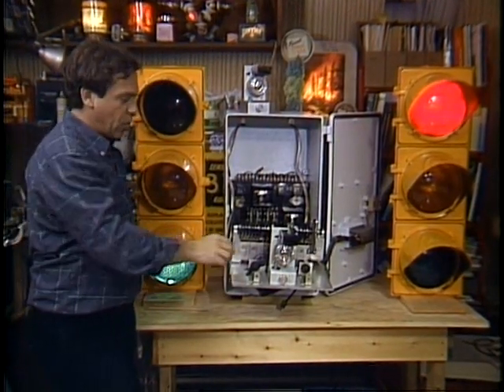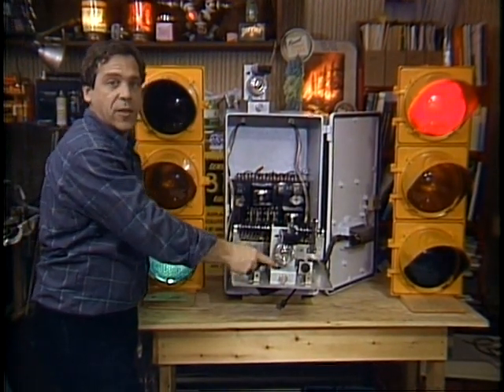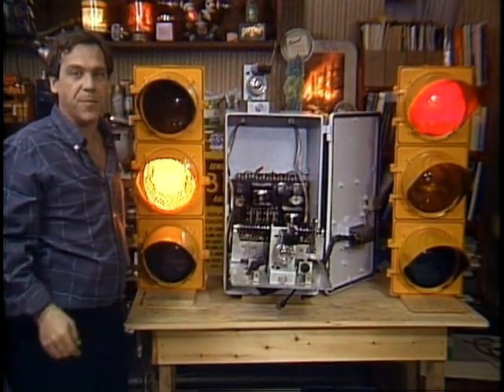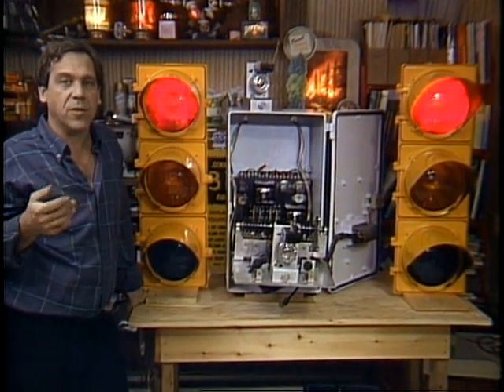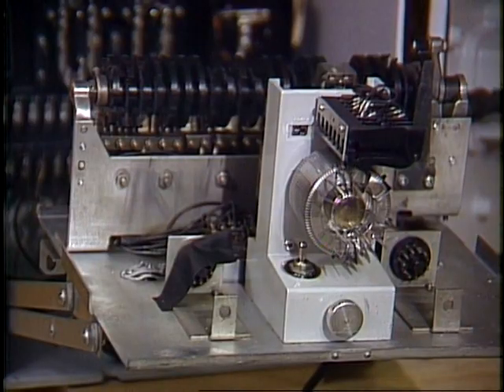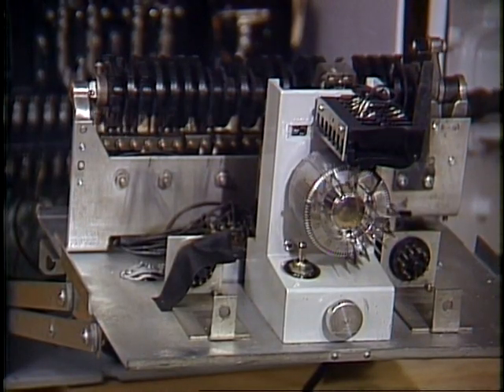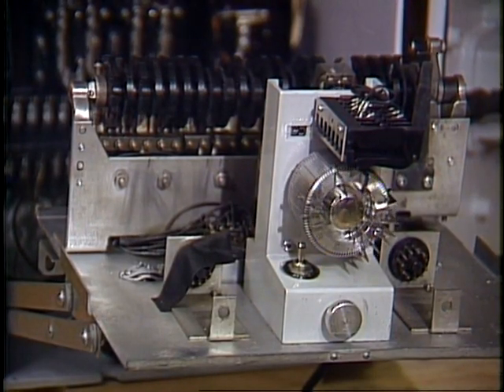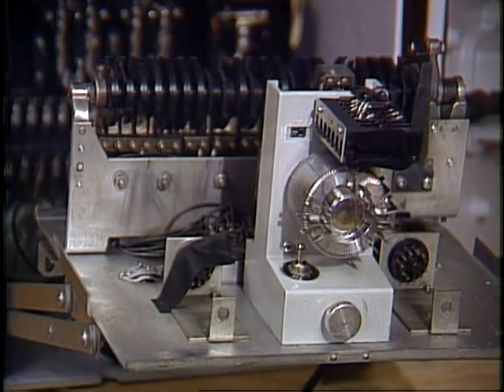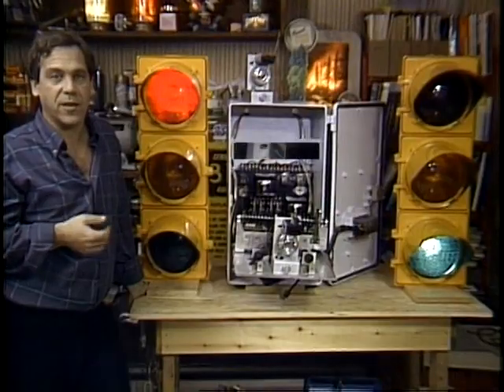Since there are 12 positions on the cam switch, there have to be 12 keys on the drum. Some of them just use up those extra positions. The ratchet advances, but no lights change. Next time you're leaning on a controller waiting to cross the street, you'll hear the ratchet advancing. Notice that some of the clunks don't affect the lights.